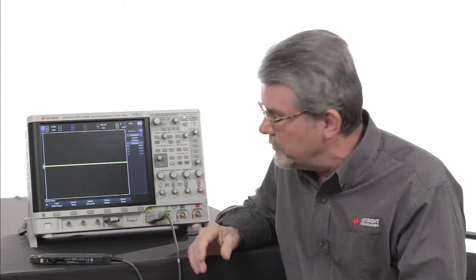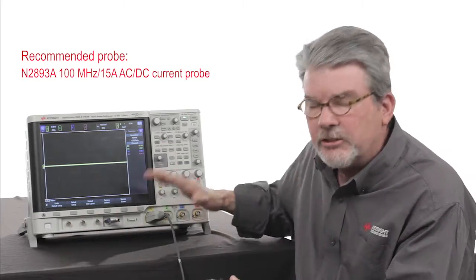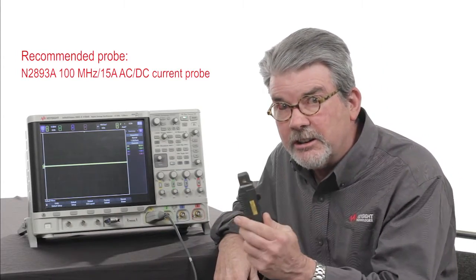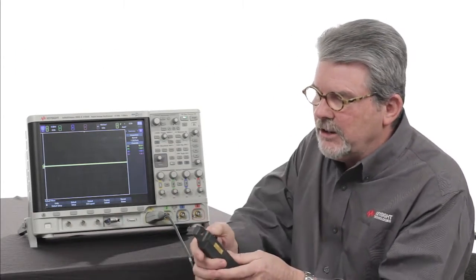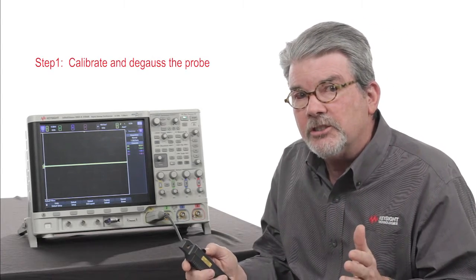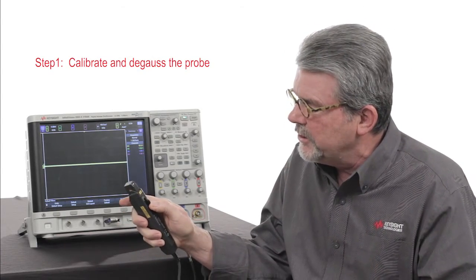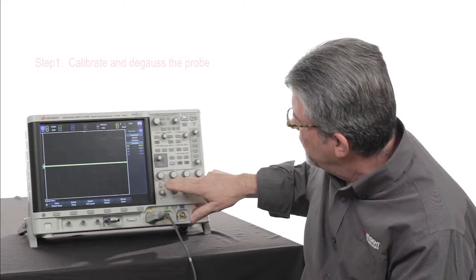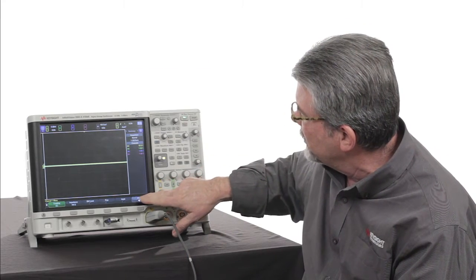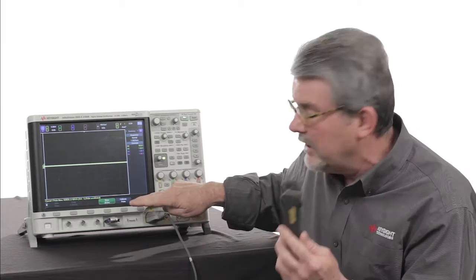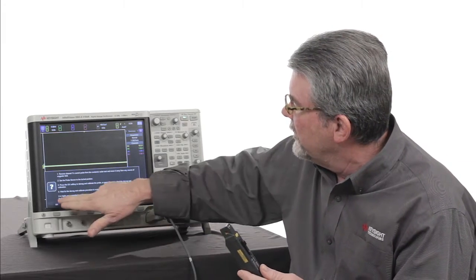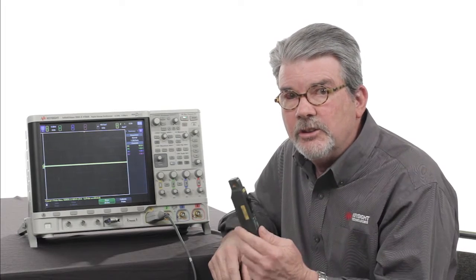The first step in making any current measurements is to connect the current probe up to the scope. Do not connect it to your DUT. You need to calibrate and degauss the probe. First of all, make sure it's fully locked. Go into the channel menu, select probe, and then select calibrate probe. The first thing it will do is automatically degauss the probe.